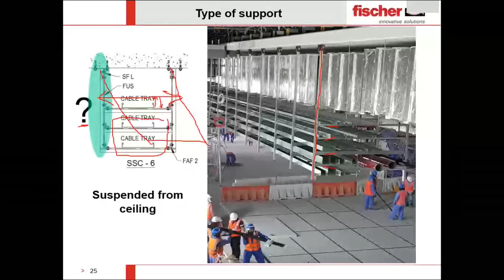Number two, some of you said seismic, which is absolutely 100% correct. When we have horizontal force like this, the system will start shaking. If it is a threaded rod, it will sway in this direction. So what will happen? We have two options: either we put a bracing with wire, or we put a rigid system. But when we have a very high drop like this, almost 4 meters from the ceiling, bracing is not recommended at all. You can put bracing, but you will not have enough surrounding area to keep that bracing, because the bracing angle must be between 30 and 60 degrees. You cannot go less than 30 degrees, and you cannot go more than 60 degrees. So this is number two.